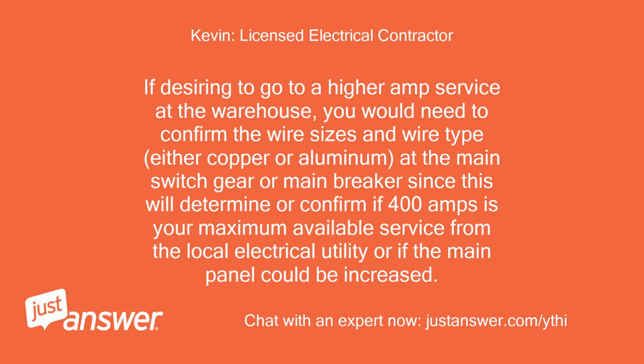If desiring to go to a higher amp service at the warehouse, you would need to confirm the wire sizes and wire type, either copper or aluminum, at the main switch gear or main breaker since this will determine or confirm if 400 amps is your maximum available service from the local electrical utility or if the main panel could be increased.